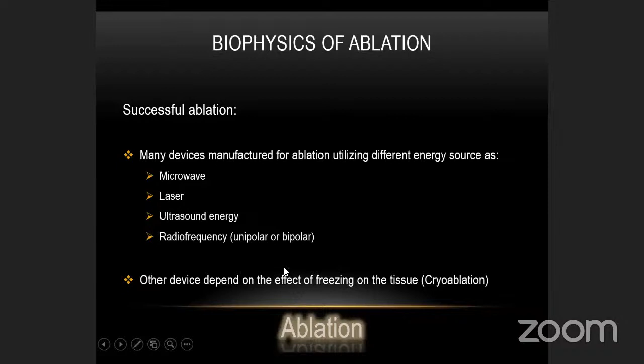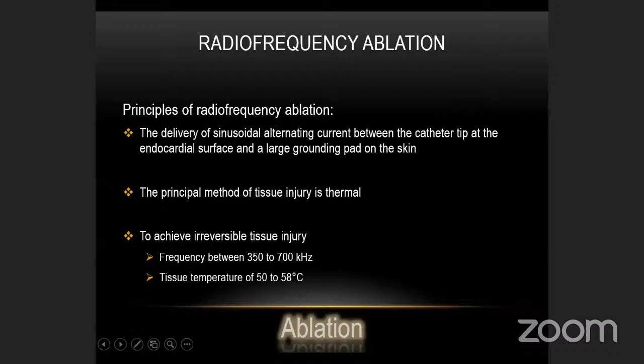Radio frequency ablation is the delivery of sinusoidal alternating current between the catheter tip and the endocardial surface, and a large grounding pad on the skin. So the principal method of tissue injury is thermal. To achieve irreversible tissue injury with radiofrequency ablation, the frequency should be between 350 and 700 kilohertz, and the tissue temperature should be between 50 and 60 degrees. Lesion size is proportional to the tissue temperature, the size of the ablation electrodes, the current and voltage, and the duration of ablation.